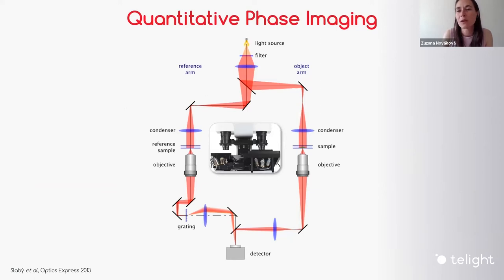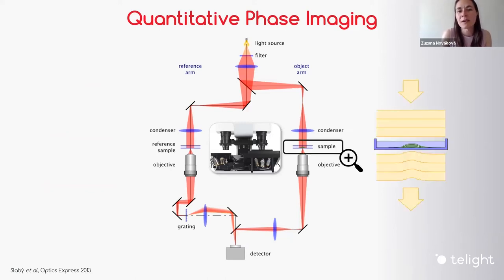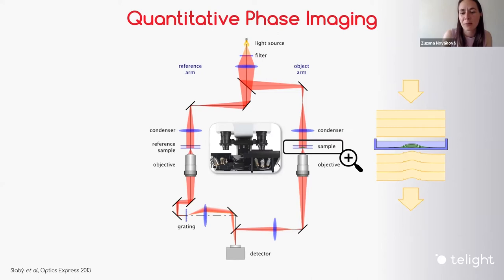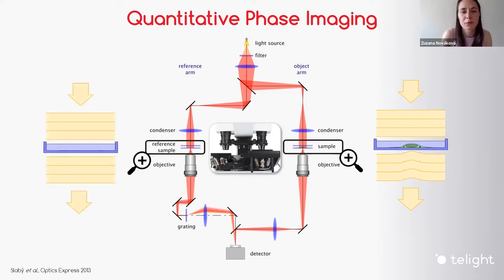In principle, what you have to do in this technology is to split the beam that comes from the light source in your microscope into two arms. One arm is called the object arm, the second one is called the reference arm. The light that passes through the cell is slightly delayed — there is a phase shift. In the reference arm, you place just a reference sample to compensate for some effects, but there is no phase shift.